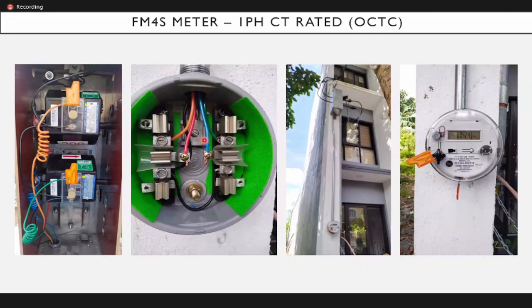Then the socket type meter base, this one, has insulation. The green insulation provides additional safety features. And there is also this insulation, the transparent. This insulation is installed at the potential terminal to ensure non-contact with current terminals. Kasi po, pag nagkaroon ng contact, baka po magkaroon ng meter burnout. The DU is the one providing all these installations. Mula po dito hanggang sa metro, DU po ang nagpo-provide niyan.